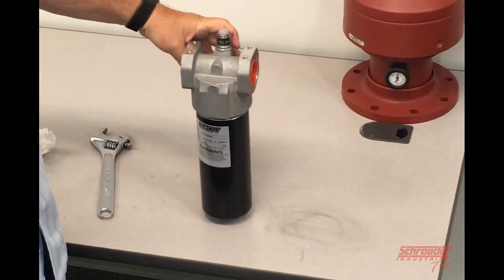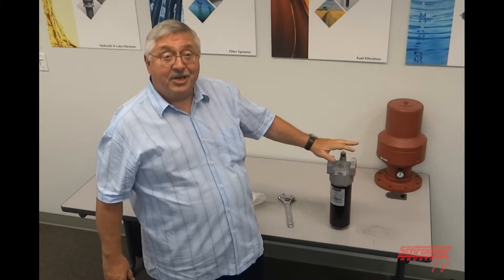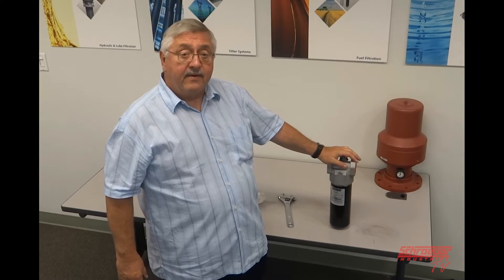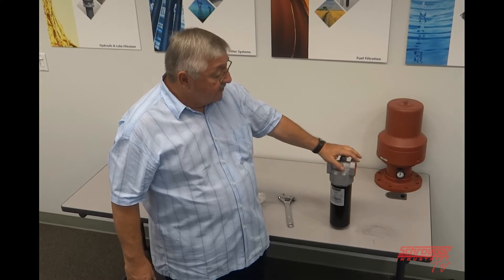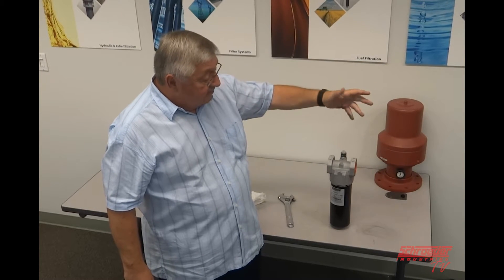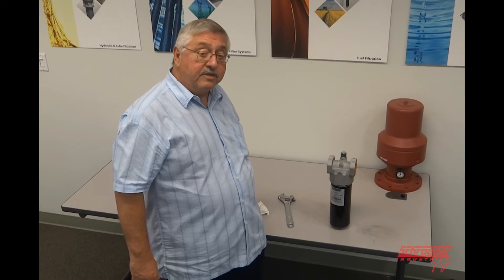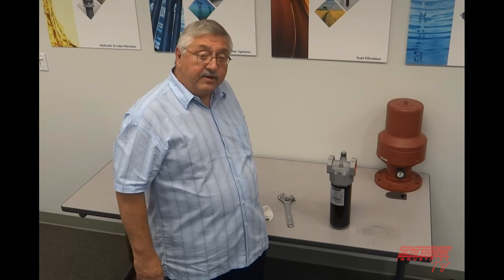Again, you've got to remember that you have your machine shut down before you do this. And if you do have to drain it, make sure you drain it. Or if you're below oil level and your reservoir is setting up, make sure you have a shutoff valve that shuts off the oil from the reservoir to the filter so you don't drain the reservoir.